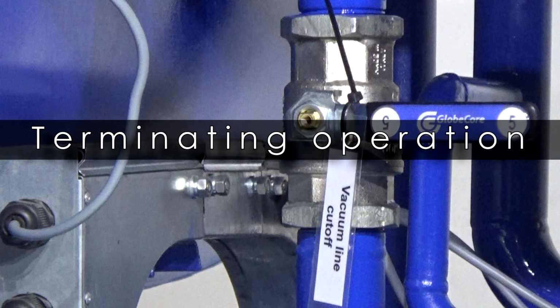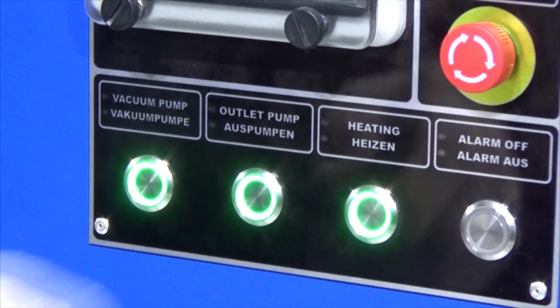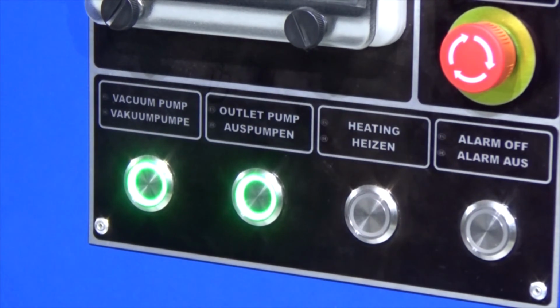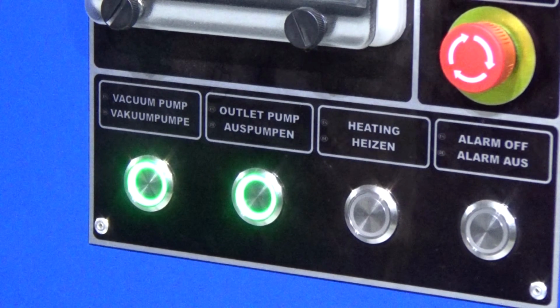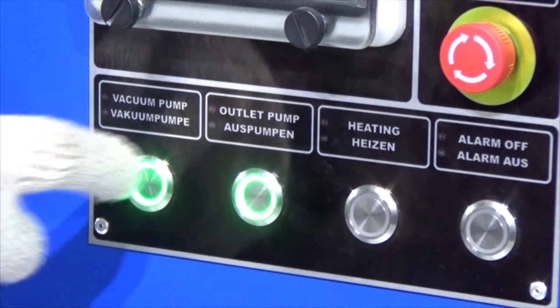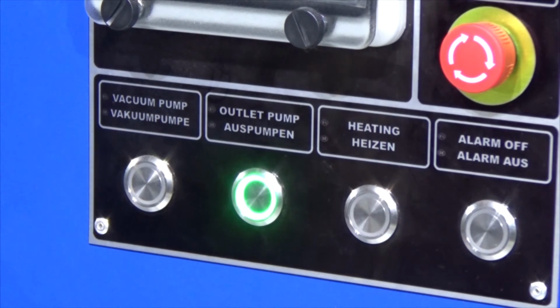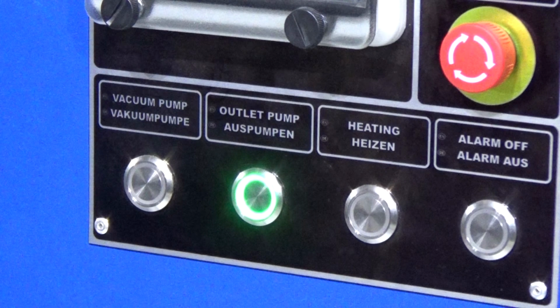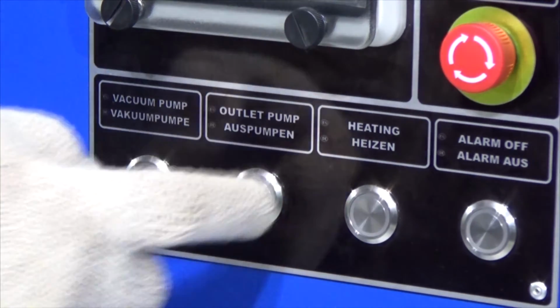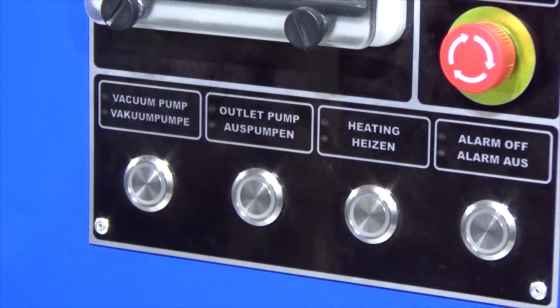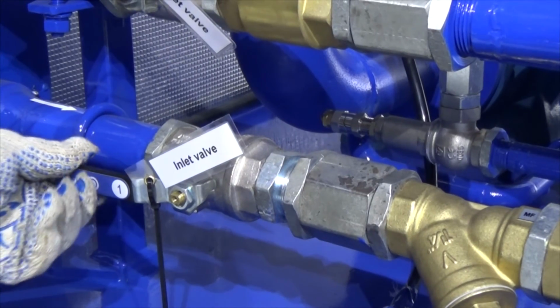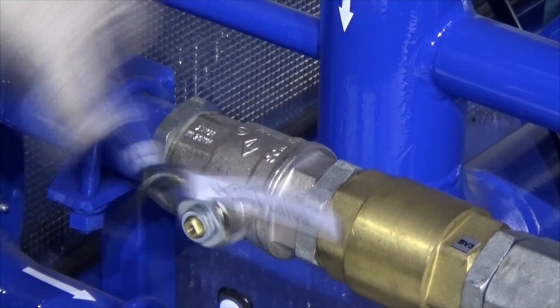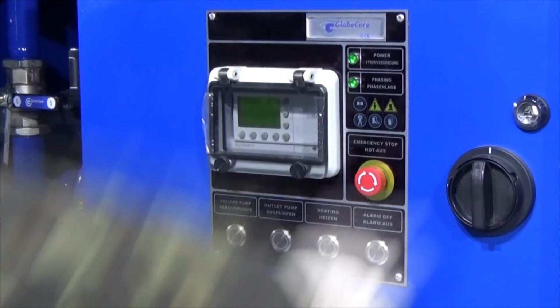Terminating the operation. 1. Disengage the heater by pressing the heating button about 5 to 10 minutes before shutting down the unit to prevent overheating of oil in the heater chamber. 2. Stop the vacuum pump by pressing the vacuum pump button. 3. After the outlet pump drive stops, disengage the pump by pressing the outlet pump button. 4. Close valves MV1, MV3, and MV5. 5. Turn the power handle to the off position.